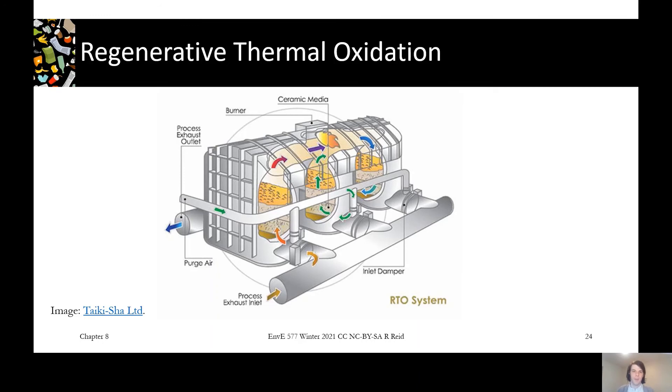Another technology is regenerative thermal oxidation and this is essentially just burning the odour compounds that are present in our odorous air and then having them come out in an oxidized form just like they would be from a biofilter. It's just using a thermal reaction instead of a biological reaction. So how this works is it's full of solid media that is going to retain the heat and then there's a little bit of fuel added to sustain a flame and then whatever air comes in is going to both provide the oxygen for the flame as well as anything that's able to combust within the odour compounds will be combusted as well.